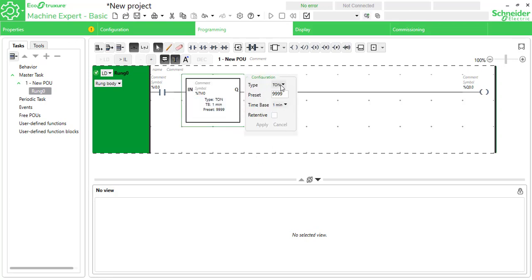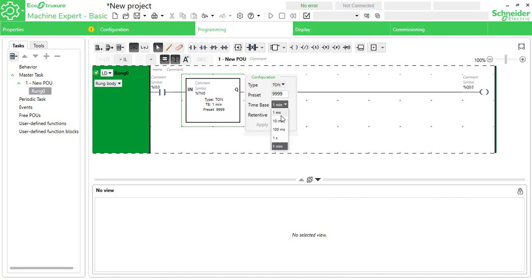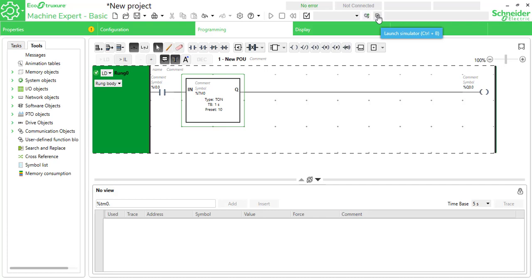Choose the timer type — it could be TON, TOF, or TP. I'm using TON. Go to preset and time base. I'm using time base one second and preset value 10, so I'll get a 10-second on-delay timing. If you want to make it retentive, you can do that too. Hit apply.